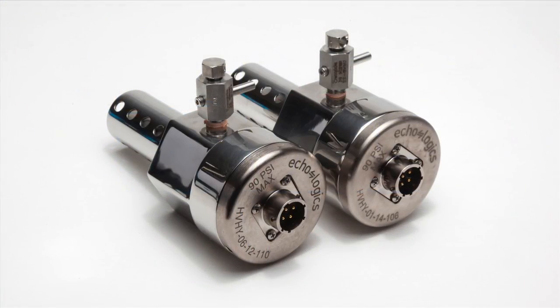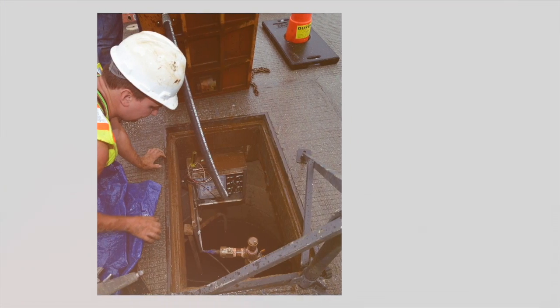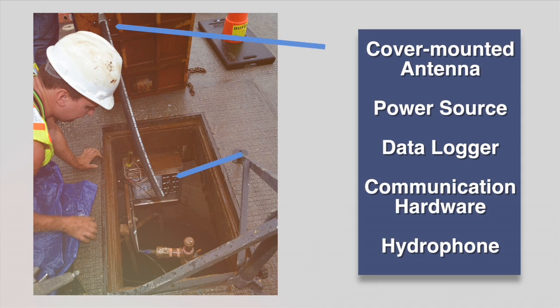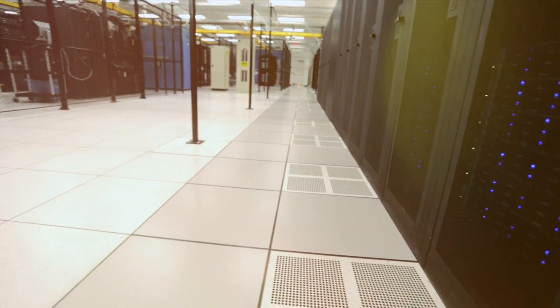A hydrophone is installed in the takeoff port of an air release valve in an access chamber along the length of the area monitored. Self-contained nodes are installed in the same access chambers where they collect synchronized acoustic data from the pipeline. Data are periodically and securely transmitted via cellular technology to EchoLogics servers over the Internet.